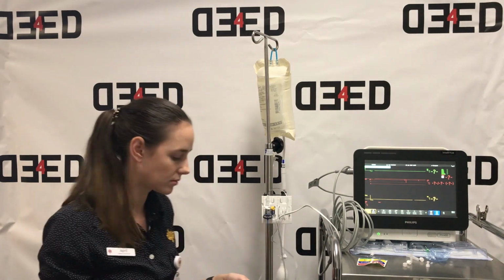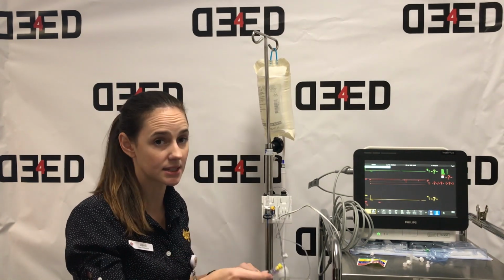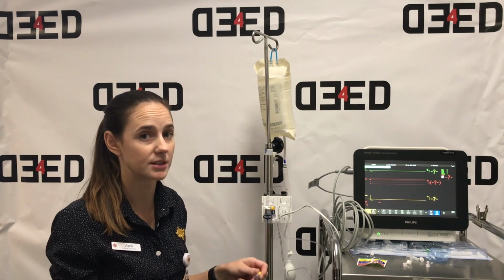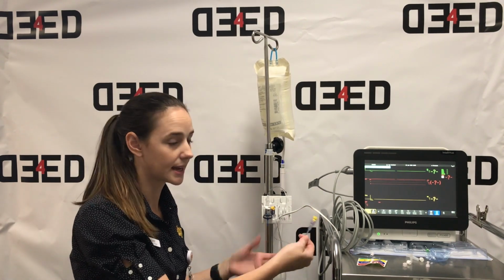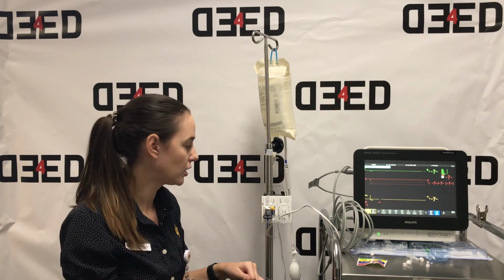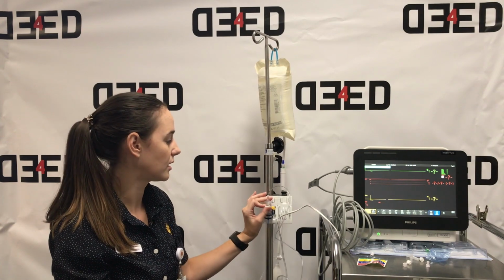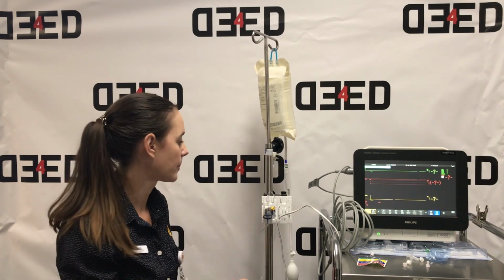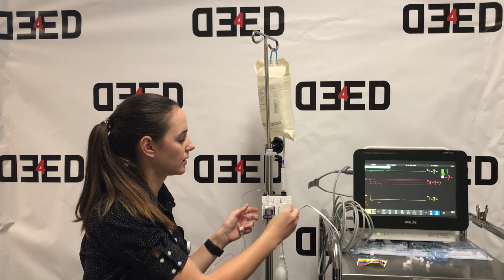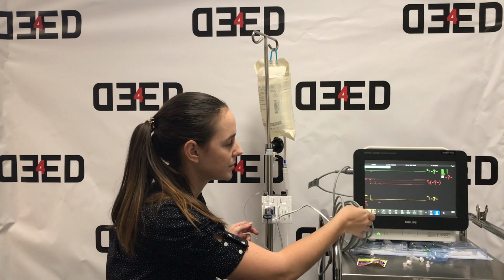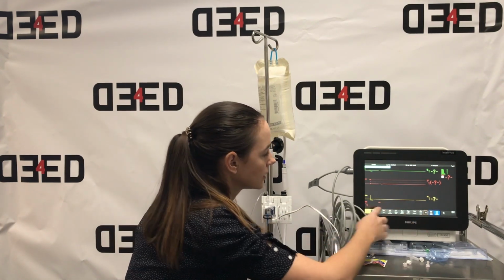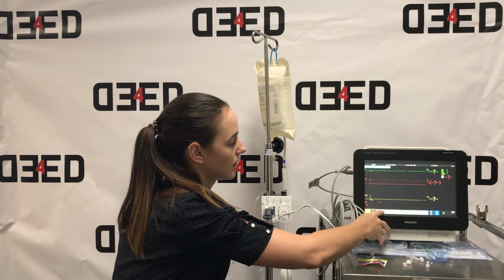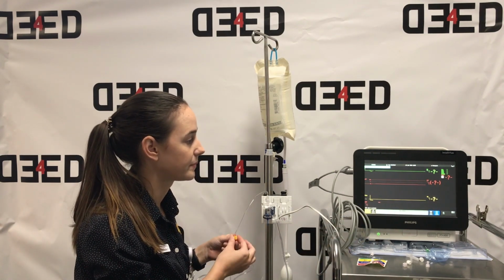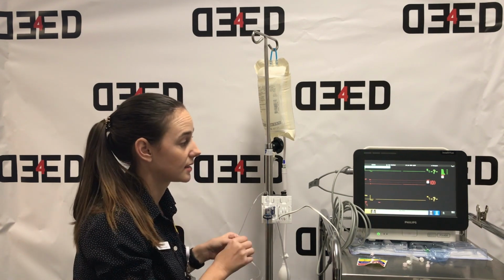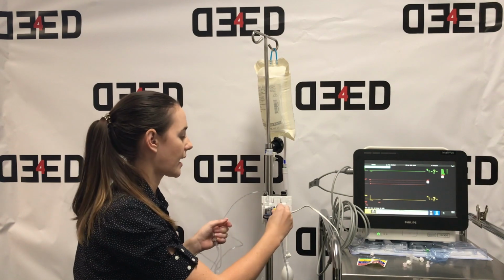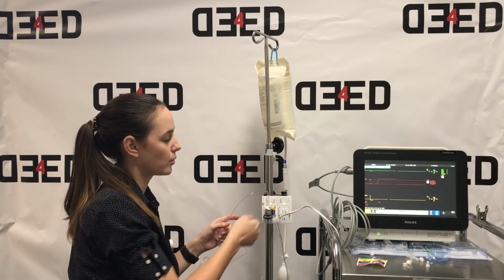So say the Artline's just been inserted and you've just connected this to your Artline. You're probably wondering how we would zero it now. So what you would do is, this is connected to the patient's end. You can do it from either port. You turn the tap off to the patient. You would then open up this port to gravity or atmosphere. Come over to your machine and find the button that says 0, press 0 and wait for it to beep. And it will then acknowledge that the 0 has been completed, 0 done. Pop that cap back on and turn it back off to the port, open to the patient.